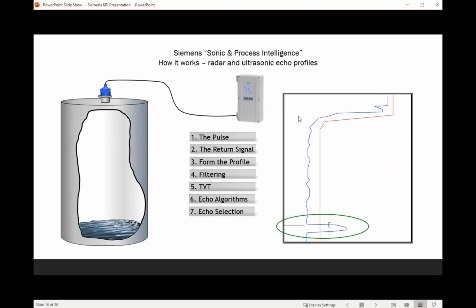That return signal measures the time of flight, and like Josh says, rate times time equals distance, divided by 2 because it's down and back, and that will give you a very accurate distance to the material itself. The next thing it does is form the echo profile over on the right-hand side, that blue line, where it drops down to the noise floor, and then at some distance you get an echo off of the material itself.